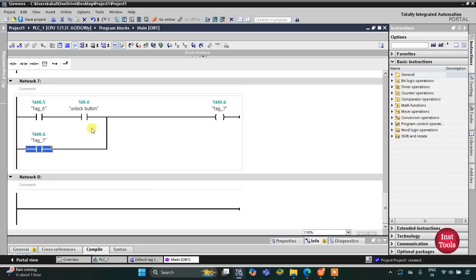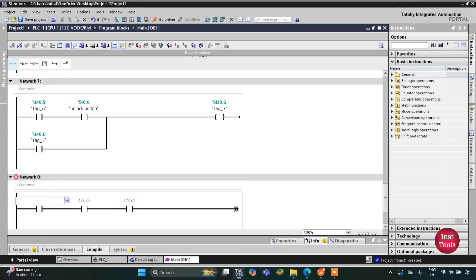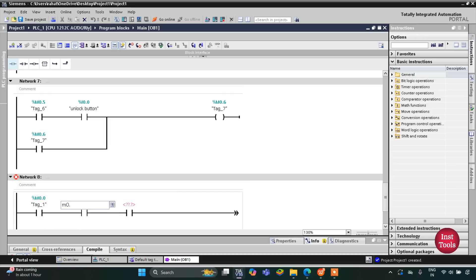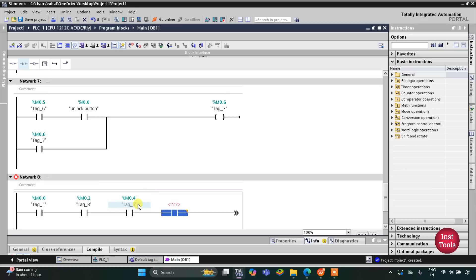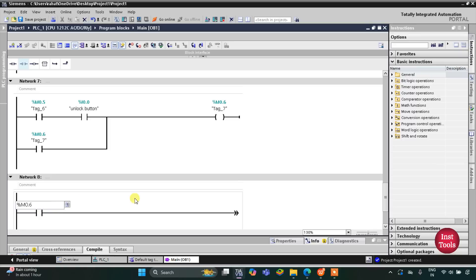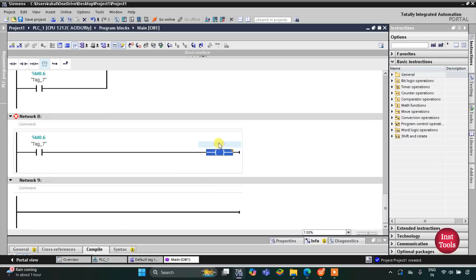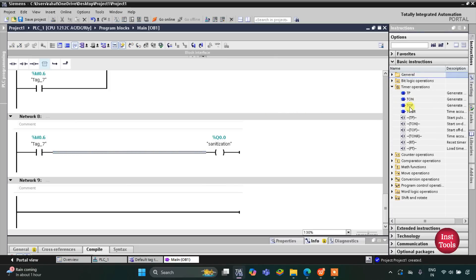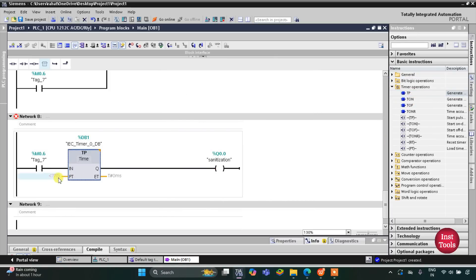The unlock button being pressed four times means the door has been opened four times. We then use the memory bit M0.6 — when it gets true — to trigger the sanitization process. This sanitization coil will activate the nozzle. The sanitization process will run for only 10 seconds, so we will use a timer operation TP with a preset value of 10 seconds.